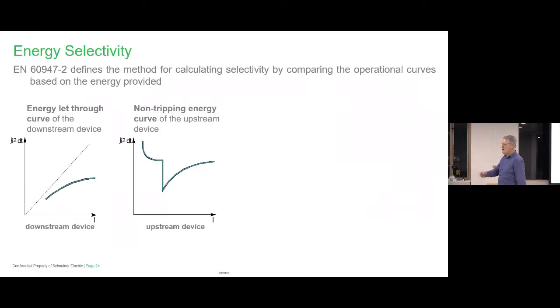And this really is a good question because it brings us into this one. So we looked at current, we looked at time, but this is energy. And this is that instantaneous side of when we're getting very, very high short circuits. So you need to compare, and as a supplier, we do that around that instantaneous value. These are the three-phase voltage short circuits that you can get. There are massive faults, so you've got to know whether the breaker can withstand it. What we call the let-through energy that can be experienced is very, very high. So we have tables like this. Not a lot of people look at these. That's very rare.